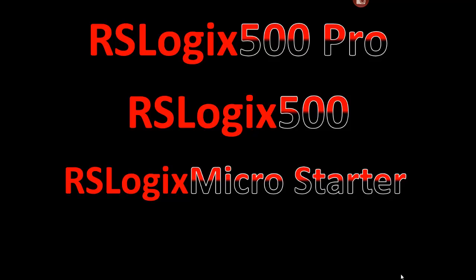And as you probably remember from other presentations, the very first MicroLogix was the 1000. And then sometime later, the MicroLogix 1200 was introduced, and then finally the MicroLogix 1500. Those three MicroLogix did not support online programming. Online programming allows you to actually edit your code online, go through several steps to test and assemble it, and do that all right online, but the 1000, the 1200, and the 1500 do not support that.